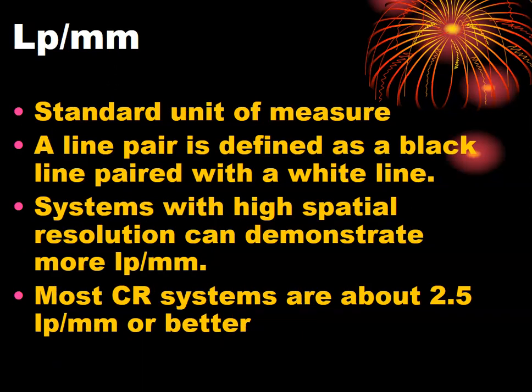Line pairs per millimeter is a standard unit of spatial resolution measurement. We take an image of a line pair test tool — a line pair is simply a black line paired with a white line — and count how many pairs fit into one millimeter. Systems with high spatial resolution can demonstrate more line pairs per millimeter. Most CR and DR systems are 2.5 line pairs per millimeter or better, with many achieving 3.5 to 4 line pairs per millimeter.